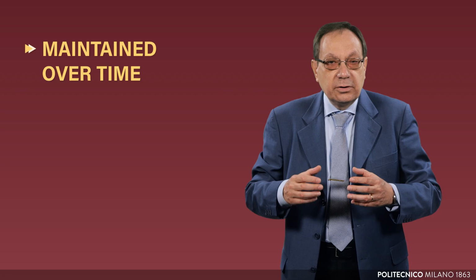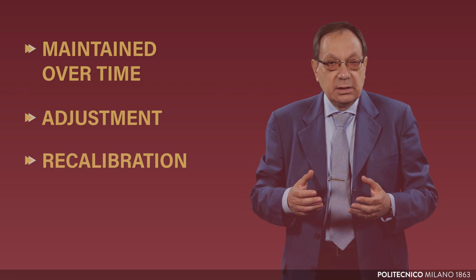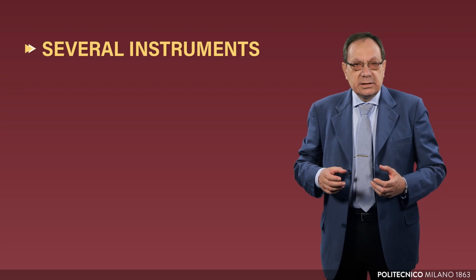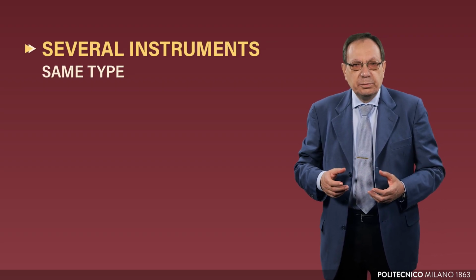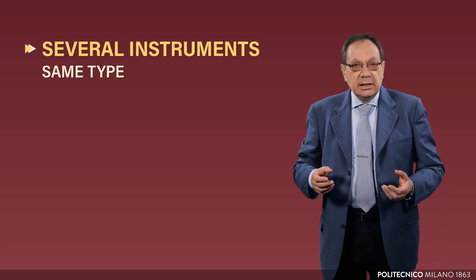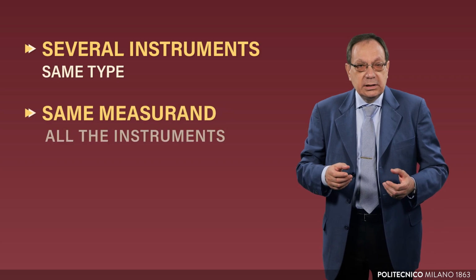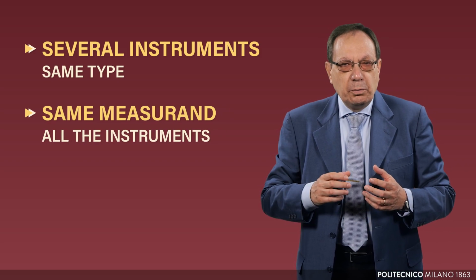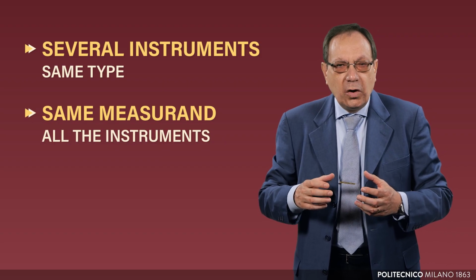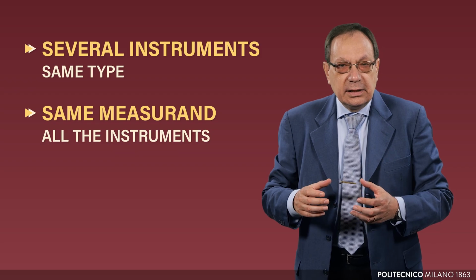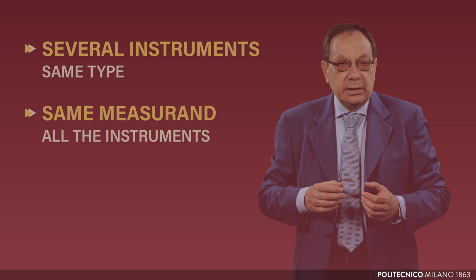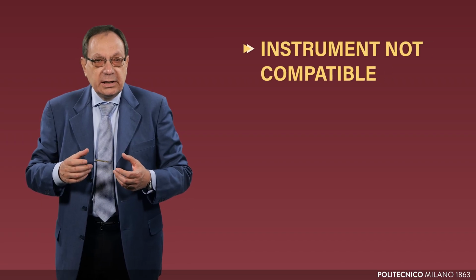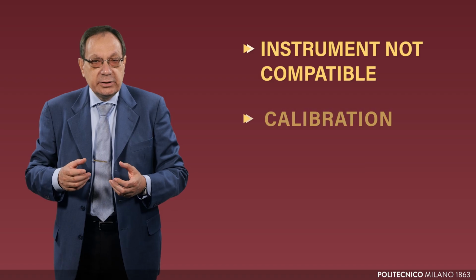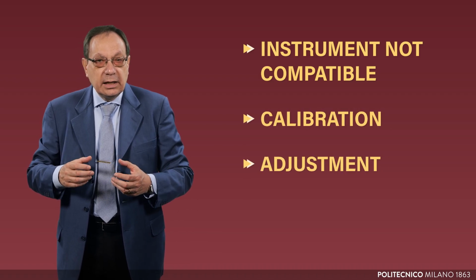These same procedures can be used to check whether the metrological characteristics have been maintained over time or whether it is necessary to carry out an adjustment and a subsequent recalibration. For example, if a laboratory has several instruments of the same type, such as a dozen calipers or a dozen voltmeters, as is typical in industrial laboratories, it is possible to measure the same measurand with all the instruments. If the results are all metrologically compatible, the characteristics have been maintained for all the instruments, as it is highly unlikely that they would all have drifted in the same way. If one of the instruments is found not to be compatible with the others, it is necessary to proceed with a calibration and, if required, with an adjustment and a new calibration.